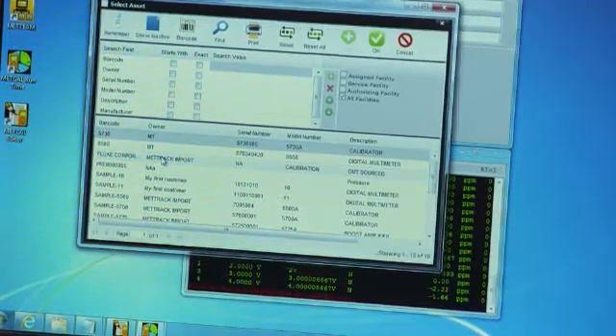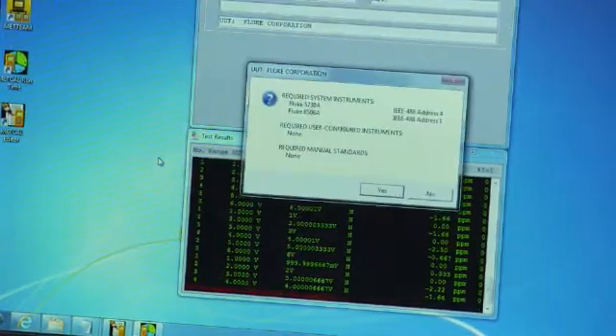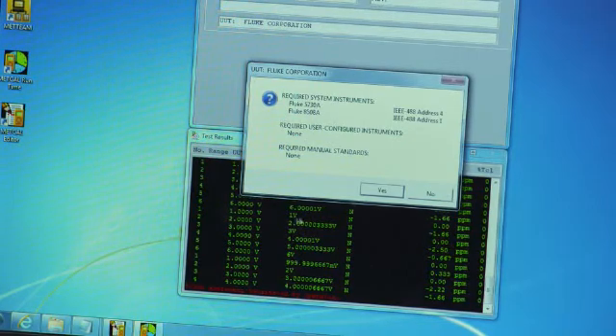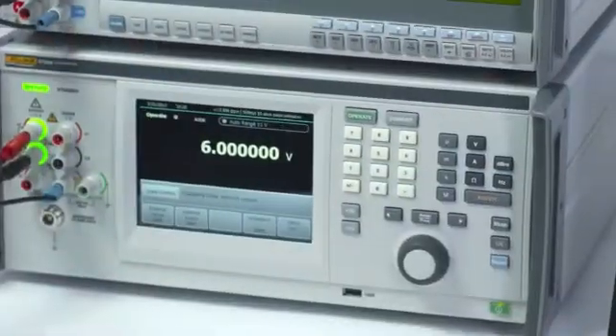The 5730A can be fully automated using MetCal calibration management software. Device mapping lets you replace an existing 5700A or 5720A in an automated calibration system without editing your library of procedures.